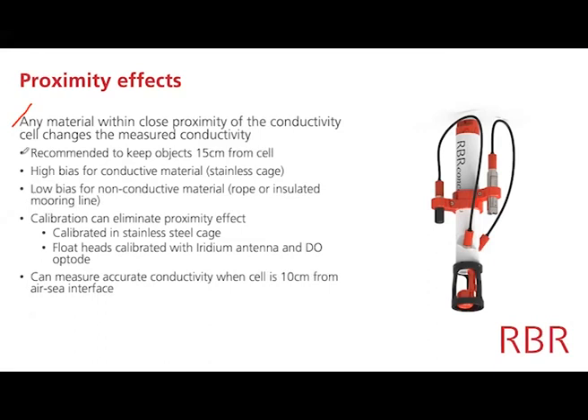And so we always recommend that the surrounding 15 centimeters of the cell, that's actually too big of a circle anyways, should be kept free of objects, unless the CTD is calibrated with that object nearby. So in this case we have a guard around the conductivity cell, but that's okay because we can calibrate it with the guard in place, and then we don't have to worry about those near field effects anymore from that particular guard. Now, if you do happen to introduce something into the field which was not there when the instrument was calibrated, you will find a bias.